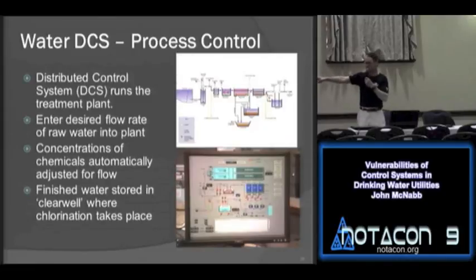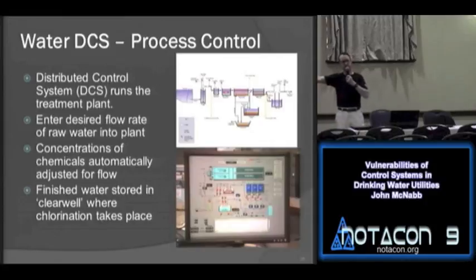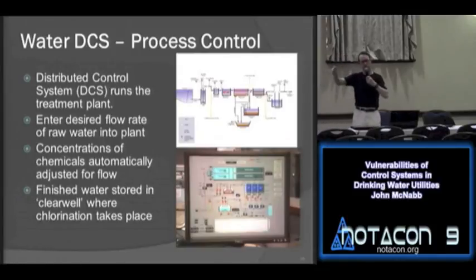You just point and click. First you have to say how much water is coming into the facility, so you set it for like 1 million gallons a day or 2 million gallons a day—we were a small plant. Then there are algorithms for the chlorination, which is now at the end of the plant, that say for this volume of water over this amount of time, you need to put in X amount of chlorine.